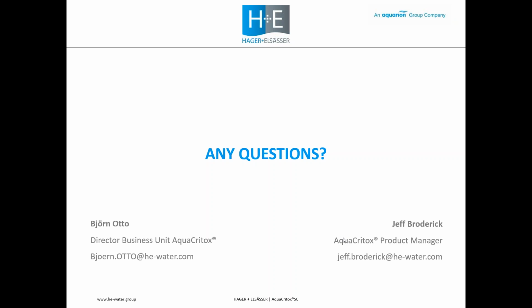Let me have a look at the numbers here. We can destroy around 120 kilograms per hour of COD using this package, and turn down is then achieved by... Let me explain this properly. Okay, so the package is designed for a limit of 50 grams per liter. If you have higher concentrations of COD, these can be accommodated by dilution.